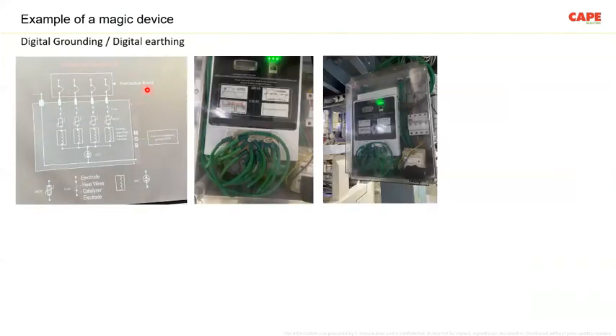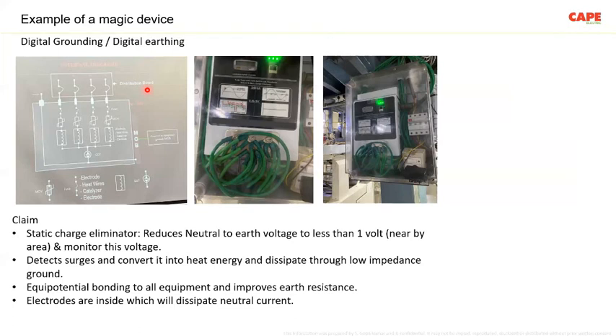One such shortcut device is becoming a real headache nowadays. I'm getting a lot of phone calls asking what this digital grounding device is. Digital grounding is a plastic box or probably a metal box, but it has a big bus bar, as you can see here. And the manufacturer claims that you connect all your devices to the bus bar, and your problems with respect to earthing, earth electrode resistance, neutral to earth voltage, surges, lightning, reverse lightning, all these problems are solved.